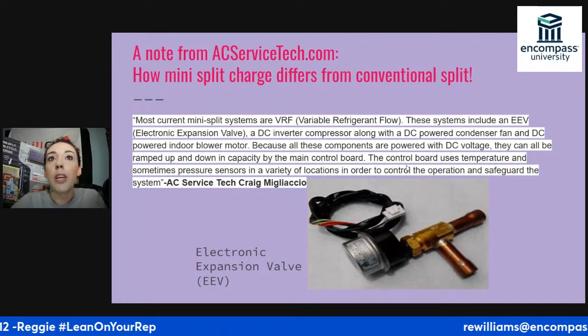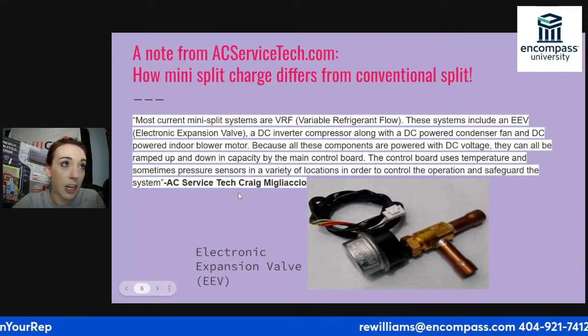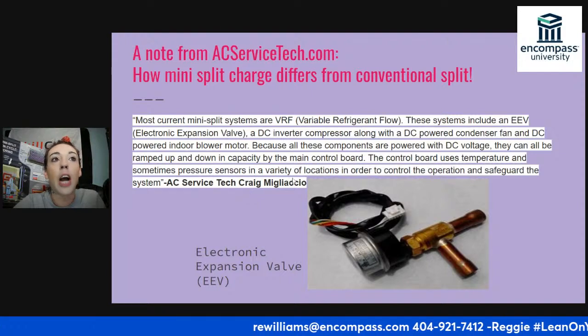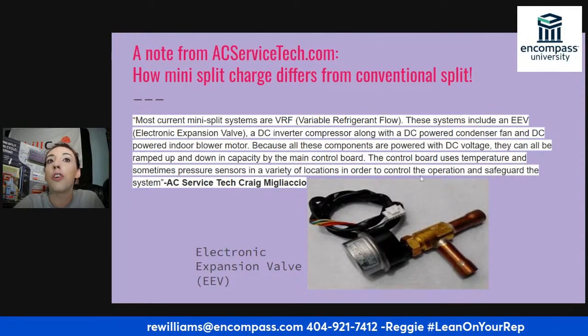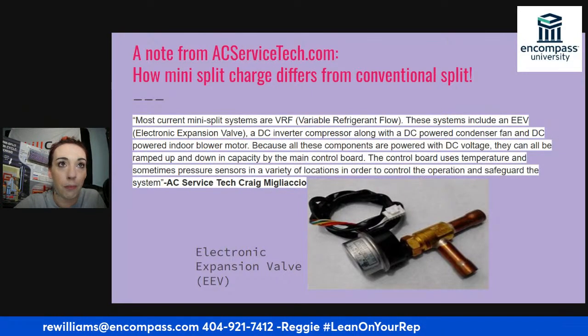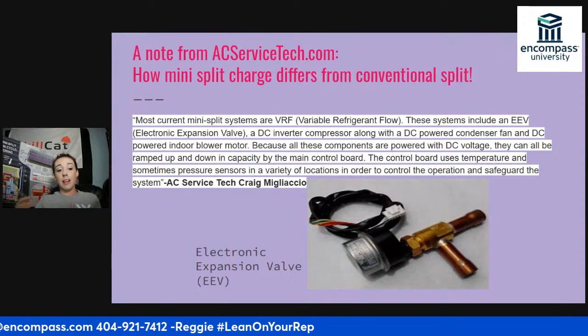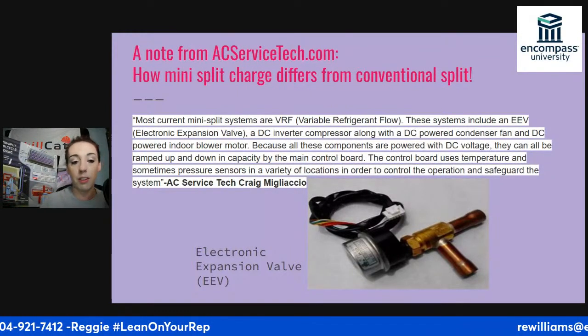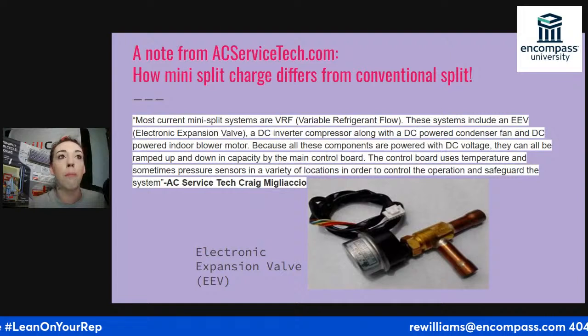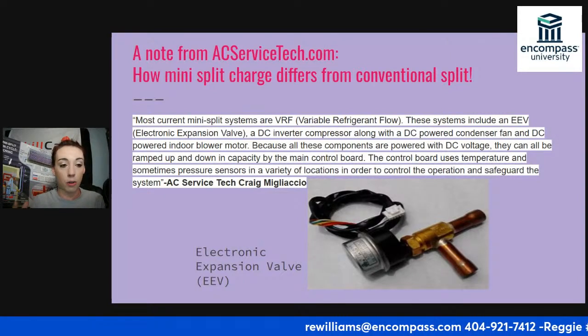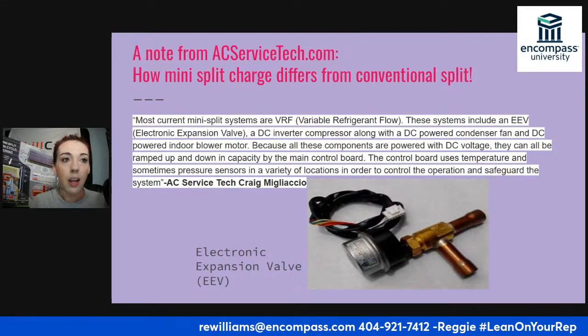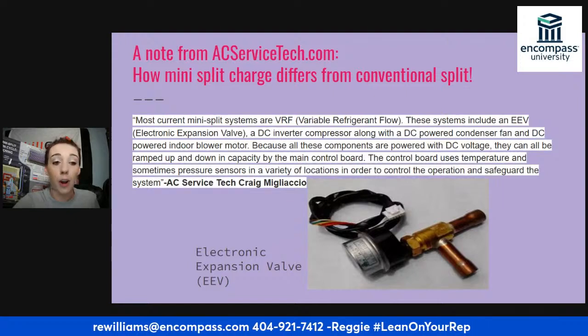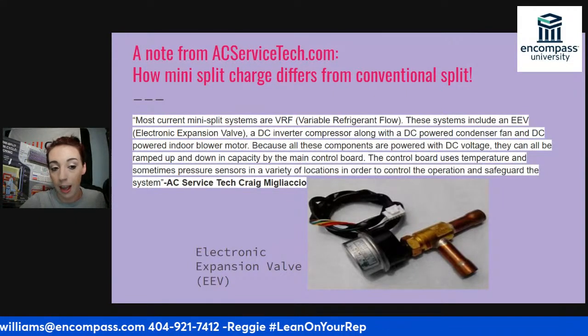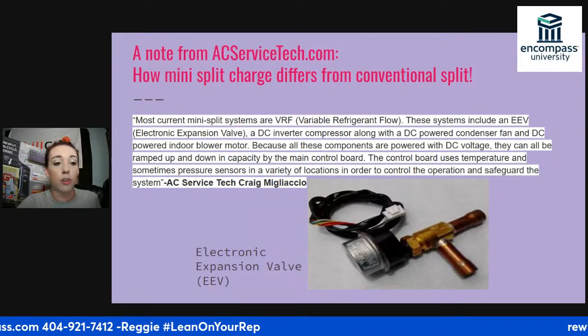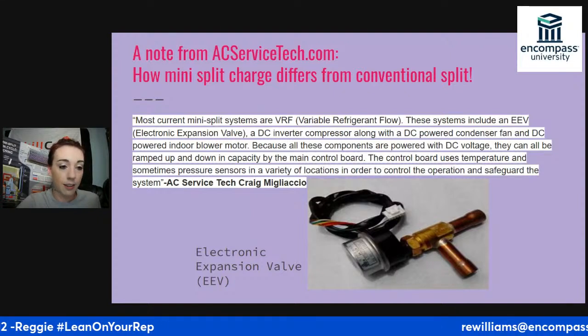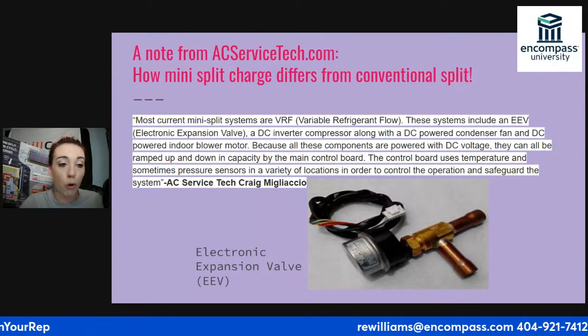So the control board uses temperature and sometimes pressure sensors, depending if it has them or not, in a variety of locations in order to control the operation and safeguard the system. So we have sensors in these mini split systems. Sometimes those sensors are made so that we know what the refrigerant has to do as far as that variable refrigerant flow. Sometimes those sensors are to safeguard the system. So if we have a high pressure switch, an HPS or an LPS, that's designed to save the compressor from low pressure or high pressure.